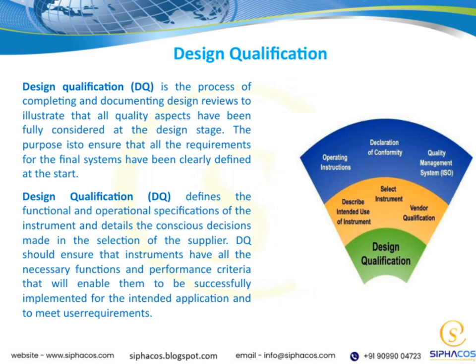Design qualification isn't just about checking boxes. It's about establishing the functional and operational specifications of the instrument. It also involves making conscious decisions, particularly when selecting suppliers, to make sure that every component aligns with our needs. Most importantly, DQ helps us confirm that the instruments we choose have all the necessary functions and performance criteria.